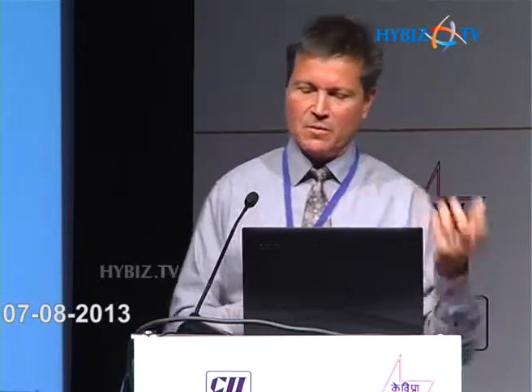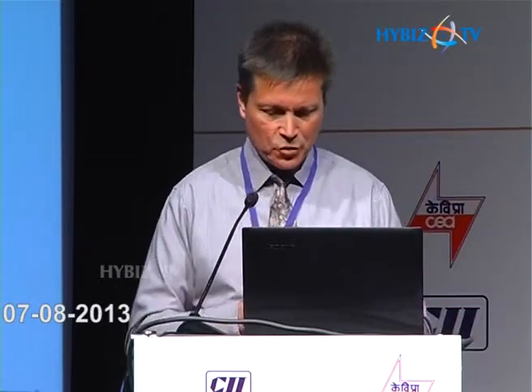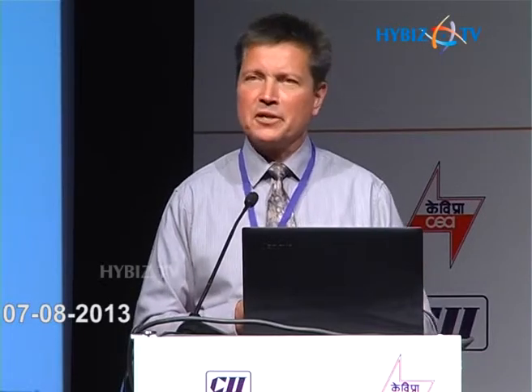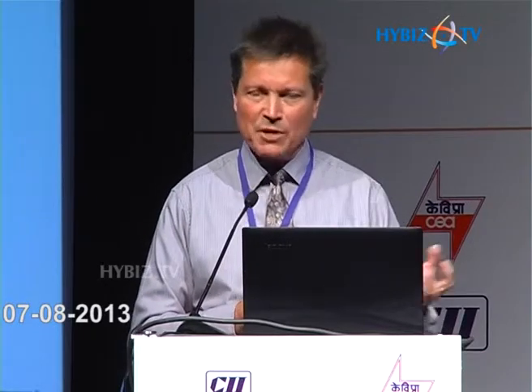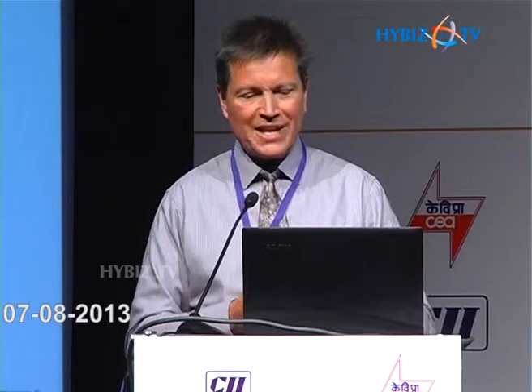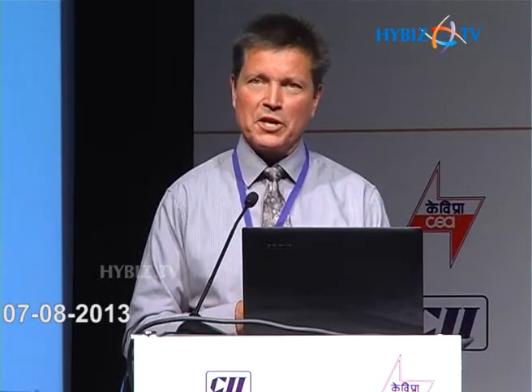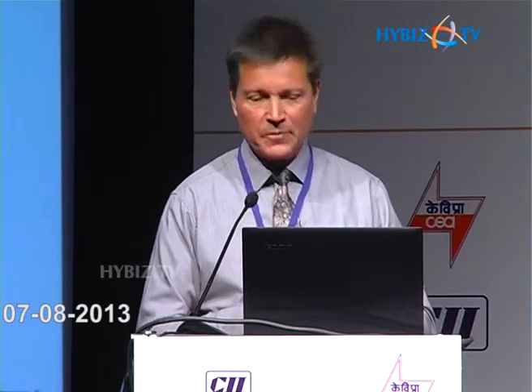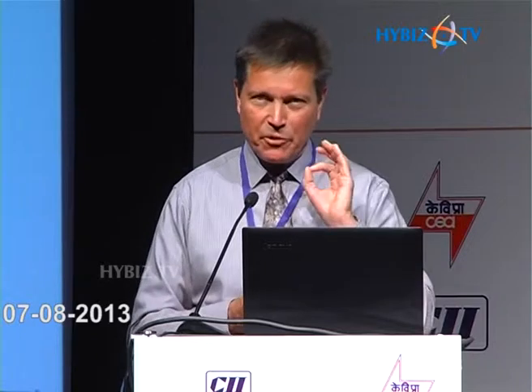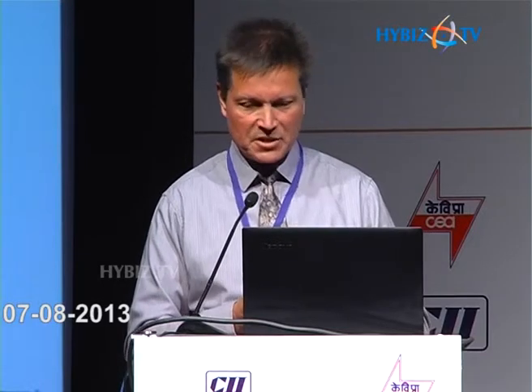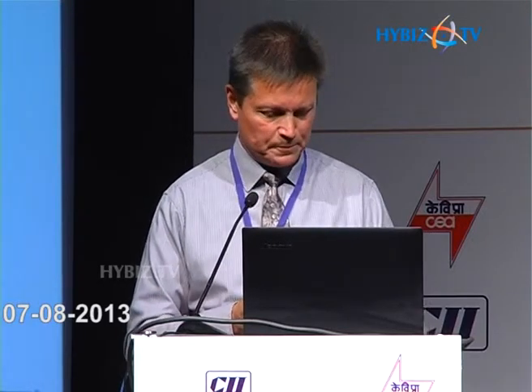We have done significant tests for the mercury systems in Europe. It's been tested by the TÜV, and we have the TÜV and MCERTS approvals, and the excellent results have given us a certified measurement range of 0 to 45 microgram per cubic meter. And of course that is perfect and specific to what you would need in a coal-fired power plant, this measurement range.